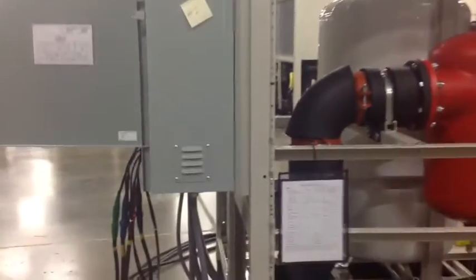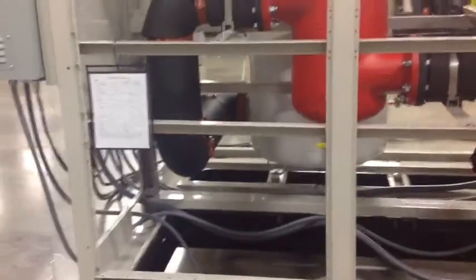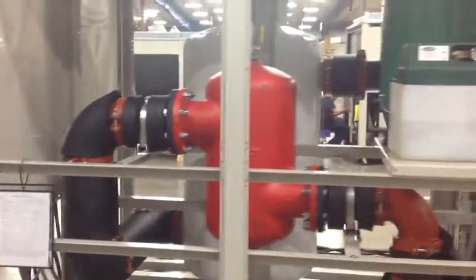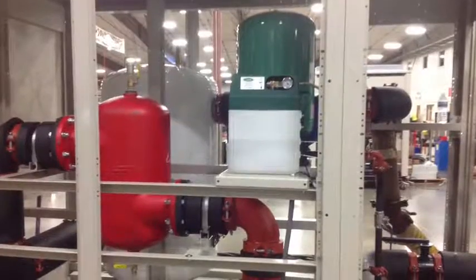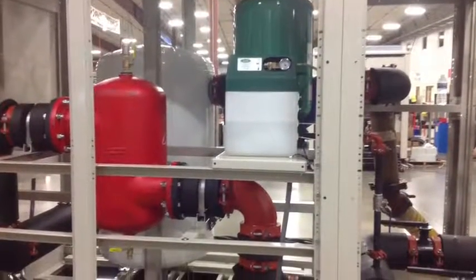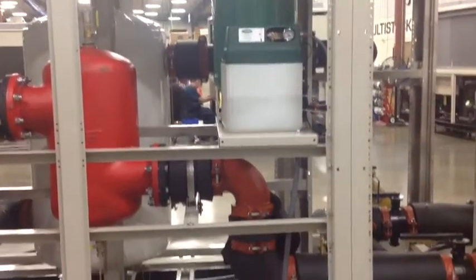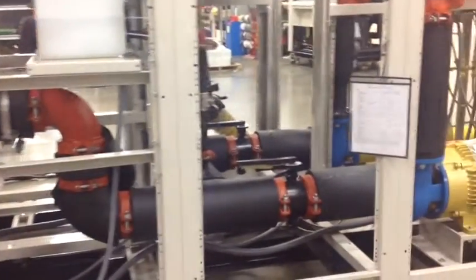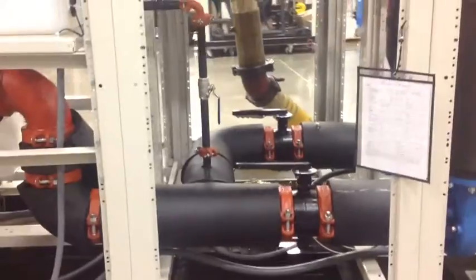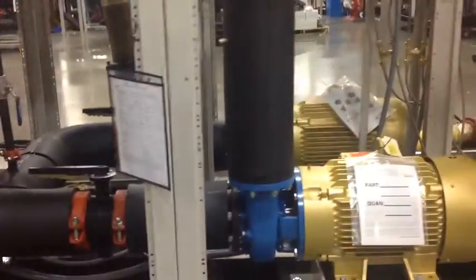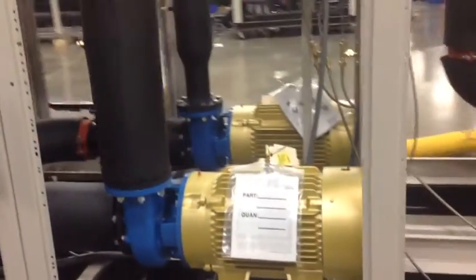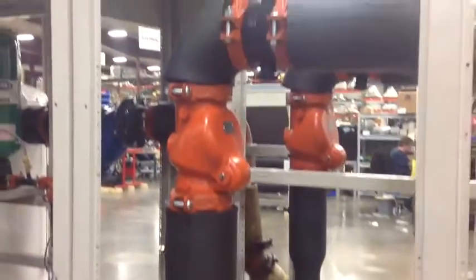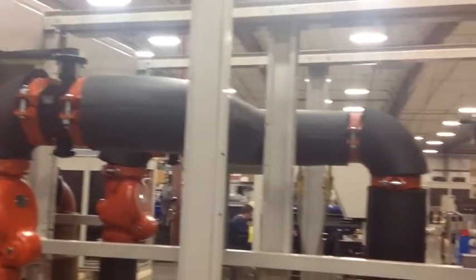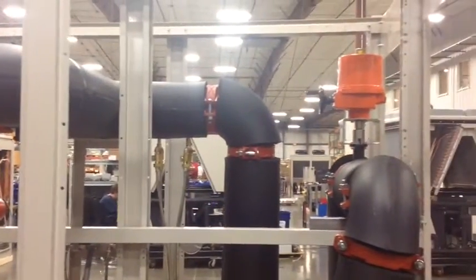Water comes from the background around and up into the air separator and then works its way right underneath the glycol mini feeder and the bladder type expansion tank before turning down to go into the pump suction. Now we move through the isolation valves into the pump suction, up through the pump discharge, check valves, isolation valves, and into the common header.